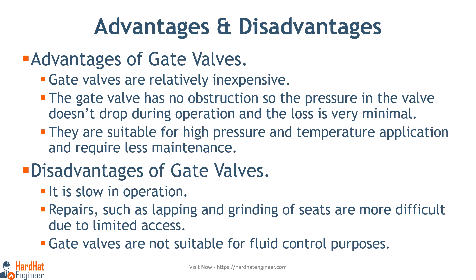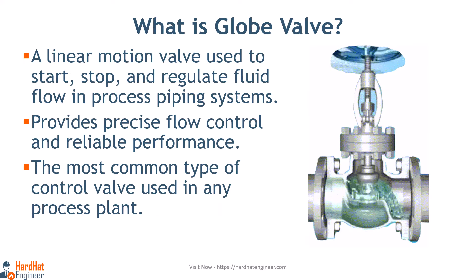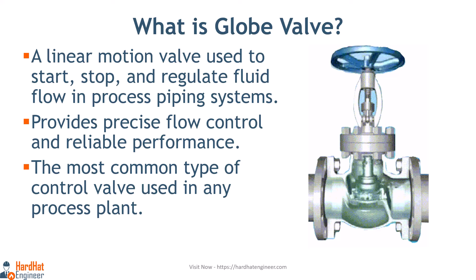Gate valves are suitable for high pressure and temperature applications and require less maintenance. Disadvantages of gate valves: they are slow in operation, repairs such as lapping and grinding of seats are more difficult due to limited access, and gate valves are not suitable for fluid control purposes.